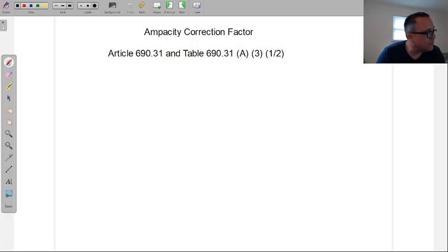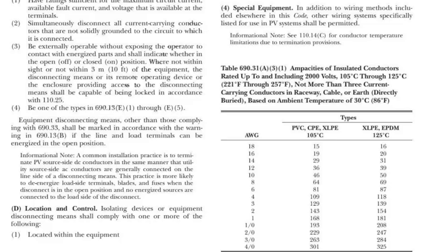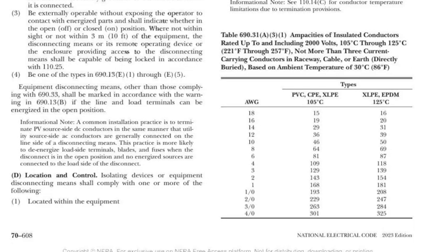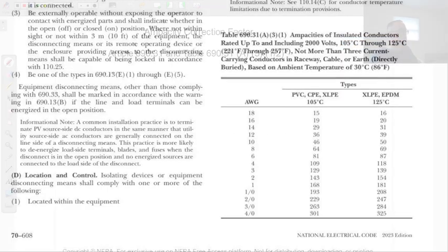But don't focus so much on the Fahrenheit because, again, we will always reference these conductors by their Celsius. Same thing, you did the 90 degree column, not the 194 Fahrenheit degree column. We still call it the 75, 60, 90. So we use the Celsius numbers. The first thing to be able to do is just to find the ampacity based off of the insulation.